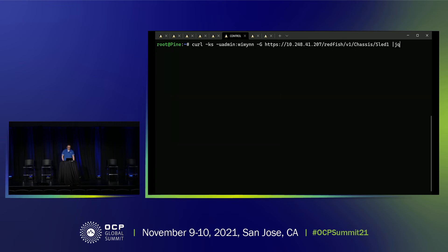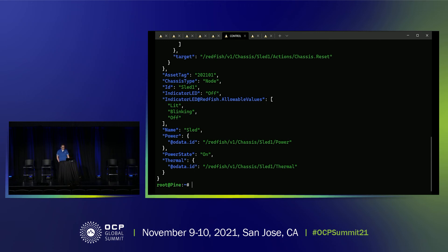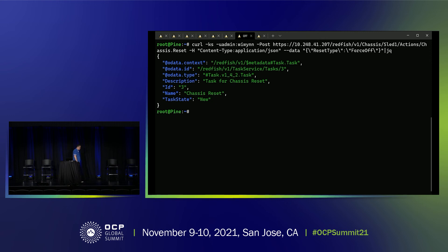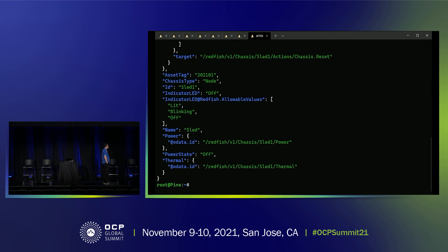Sled chassis control supports power on, off, and cycle actions. Here we demo the power case. You can see the current sled 1 power state is on. We perform chassis power control on sled 1 by using a Redfish force action to send a JSON payload into the API, using force off to turn off the sled chassis power. RMC creates a task for the sled power action, then sends the power command to the sled through IPMB. After several seconds, we can check the power state of sled 1, and you can see its power state is now off.